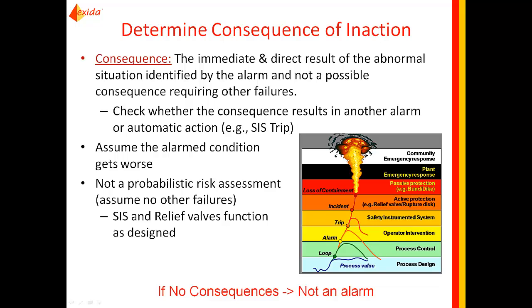We next analyze the potential consequences of inaction, focusing on the direct and immediate result of the abnormal situation, not what could happen after a series of failures. Another way to think about it is: what consequences can the operator prevent directly by taking the appropriate corrective action? This consequence assessment is different from a Process Hazard Analysis, or PHA. In a PHA, one is after the ultimate consequence — what could happen if all layers of protection fail. In alarm rationalization, we are only interested in the direct and immediate consequence of failing to respond to the alarm.